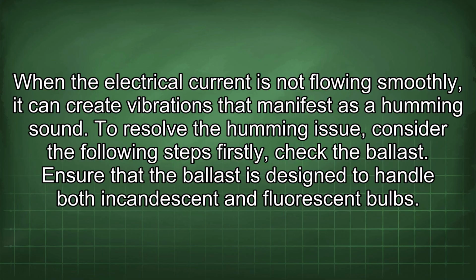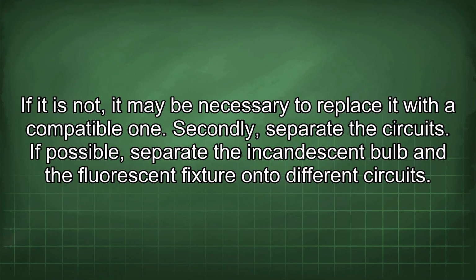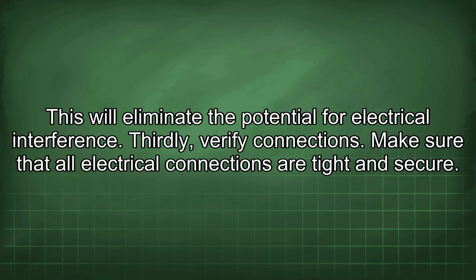To resolve the humming issue, consider the following steps. Firstly, check the ballast. Ensure that the ballast is designed to handle both incandescent and fluorescent bulbs. If it is not, it may be necessary to replace it with a compatible one. Secondly, separate the circuits. If possible, separate the incandescent bulb and the fluorescent fixture onto different circuits. This will eliminate the potential for electrical interference.